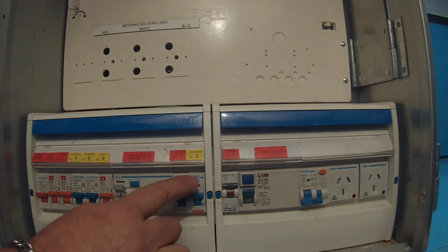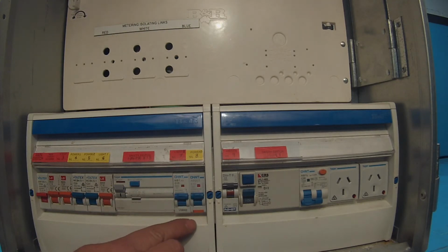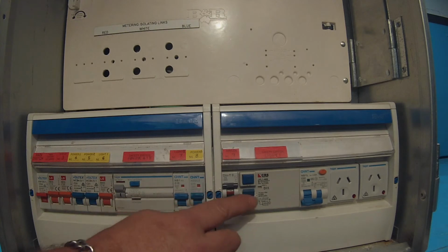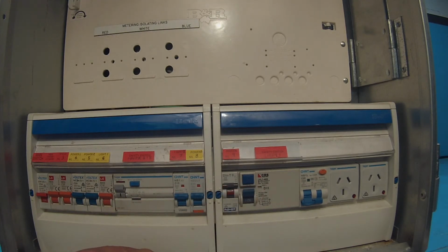Additionally, you've got power 3 here. You may have one of these on your switchboard. This is a combination device of circuit breaker and safety switch in one. You'll note here the orange test button down the bottom. It's very different from the other two safety switches that I've just shown you, but it's a combination safety switch circuit breaker, and this is the test button for it.